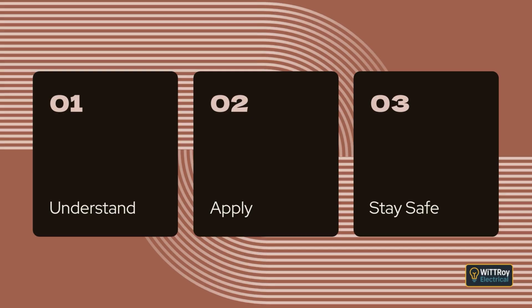Fifth, the design must consider the needs of the user and how they will operate the installation. Sixth, wiring colors must comply with the rules. Green, yellow, or green/yellow are only for earthing conductors. They must never be used for active or neutral conductors. Seventh, socket outlet polarity must be correct and must be consistent throughout the installation. And finally, semi-enclosed rewirable fuses cannot be installed. They are not permitted. In simple terms, install equipment safely, mount it securely, wire it correctly, follow the instructions, and ensure the installation suits its environment.